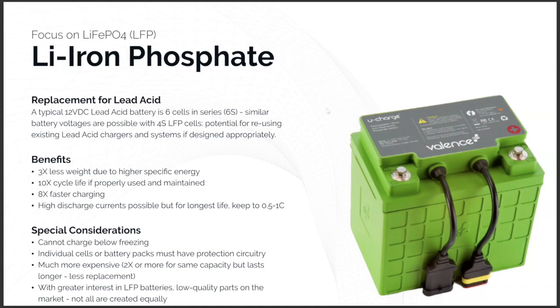Again, you don't necessarily always want to assume that, but the benefits versus lead acid: you've got much lighter weight because it has higher specific energy, more cycle life especially if properly maintained, and you can recharge it more often, or many more times. It can potentially have much faster charging - we all know it takes a long time to charge a lead acid battery. Discharge currents can be high too, but to have it well maintained, you want to keep it to around 0.5 to 1C. You don't want to really try to drain the life out of it with a heavy load.